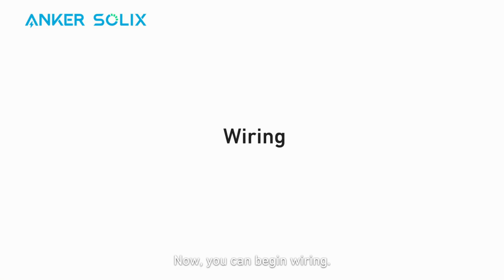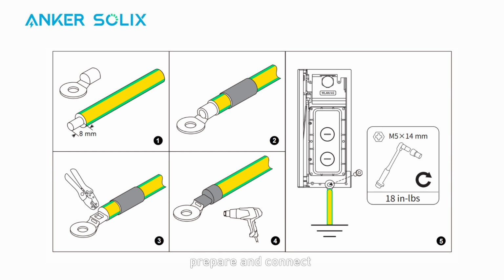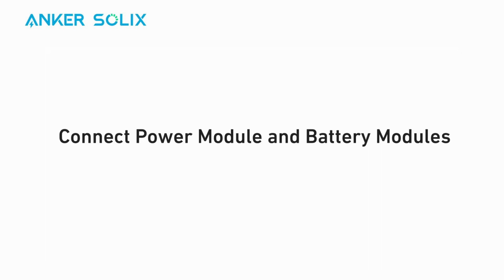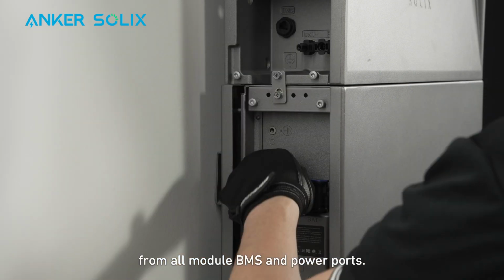Now, you can begin wiring. First and foremost, prepare and connect a ground cable from the power module to the external ground point. Remove the dust-proof plugs from all module BMS and power ports.